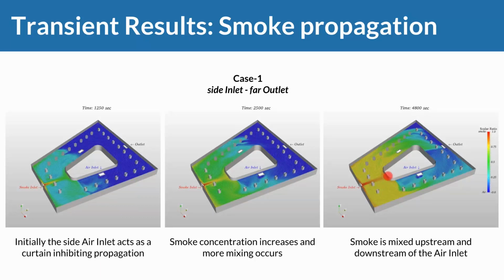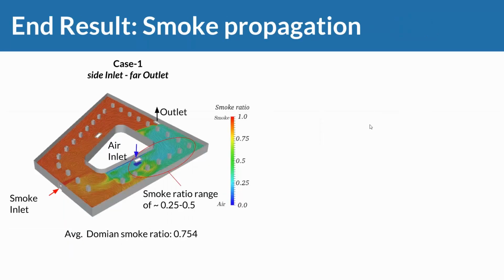is sort of at full smoke concentration, right? 100% smoke concentration. And yellow basically means more smoke, so visibility factors would be worse, and obviously air quality is worse. And we can see that this part is sort of safe here, but the rest is pretty much filled up. And we can now compare this with another HVAC operating mode.